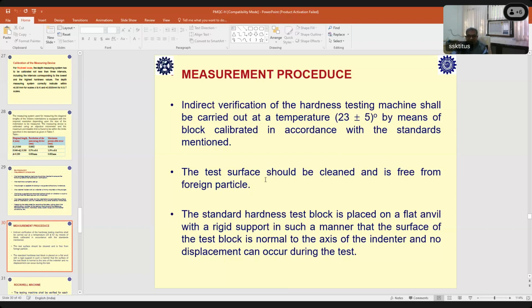So the test surface should be clean and free from foreign particles. I have already mentioned this, and it is also clearly written: your test surface should be highly polished, and both the surfaces are important. Sometimes we don't pay much attention to the supporting surface. The top surface, on which you are making the hardness measurement, is well polished, and perhaps they apply oil and maintain it, and it is clean. So when you are making the measurement, you wipe out that oil and make the measurement on the top surface. At the same time, we don't pay much attention to the bottom surface, because there can be rusting and other things. So the bottom surface is also equally important, because that is a supporting surface.